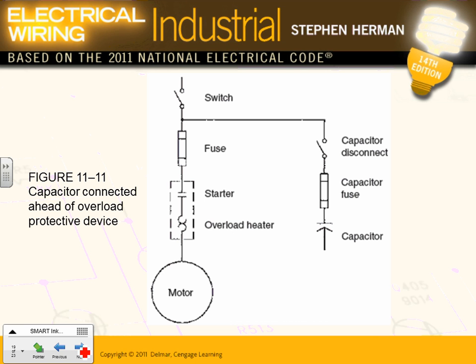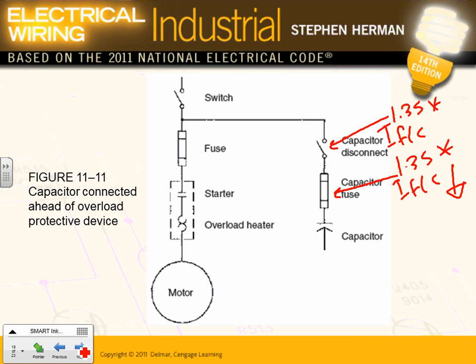If you do it this way, then I need to size my disconnect 1.35 times full load current for the capacitor. My fuse, typically 1.35 times full load current. If it's not a standard size, we go down. My conductors, same thing, 1.35 times full load current. That's how we size all these conductors that feed your capacitor. And then you take from the disconnect size here, and you have a disconnect for your capacitor.